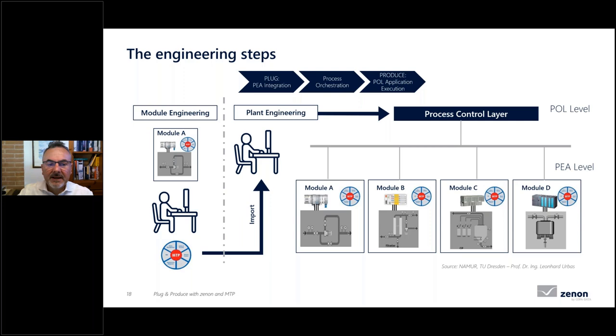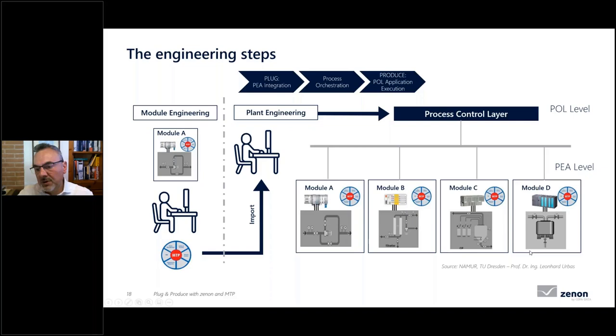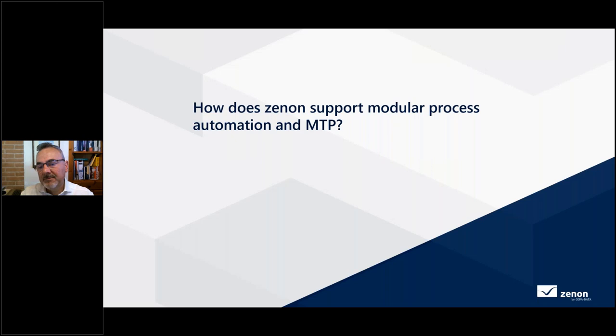Summarizing the engineering steps: module engineering involves an engineer providing automation for a specific module — PLC programming — and generating the MTP file. Separately, a plant engineer uses the MTP description and OPC UA communication to plug every module, orchestrate the modules, and produce the application. Modules A, B, and C can have different PLC types but share the common MTP description and OPC UA communication. This is exactly the engineering workflow.